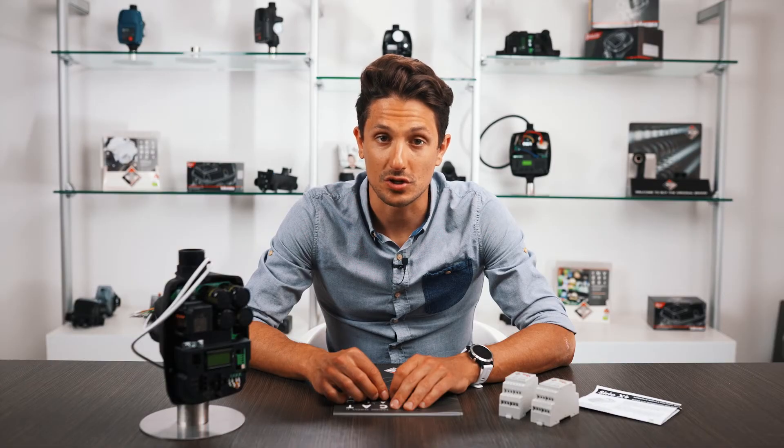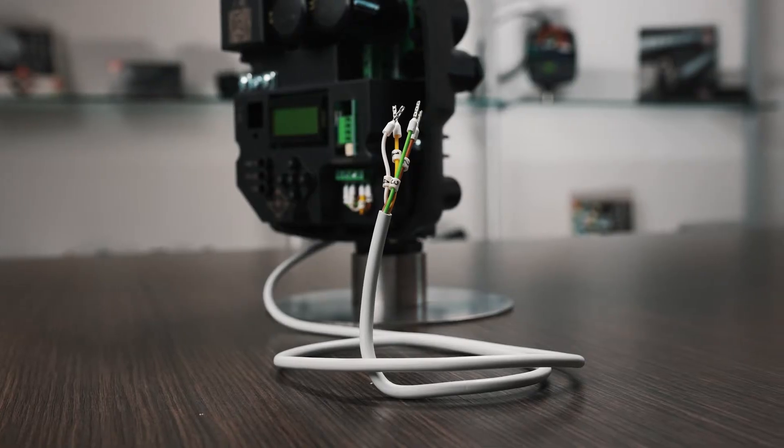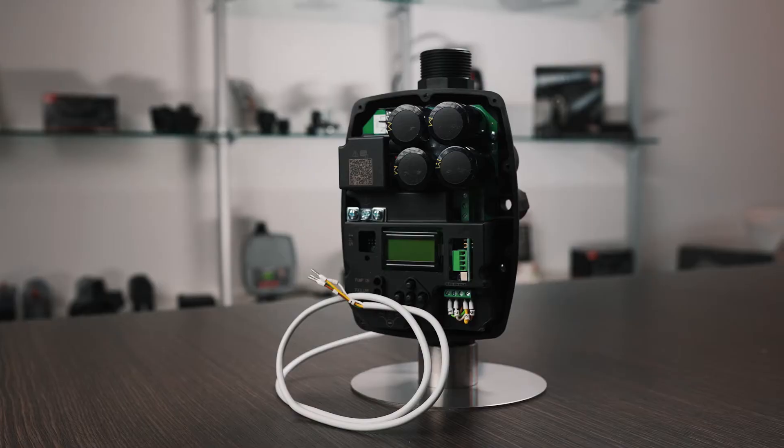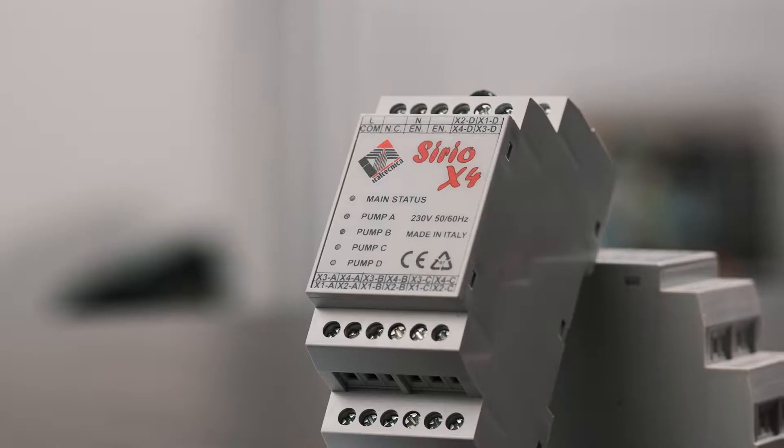If we have twin groups — meaning groups with two pumps — a device must be associated with each pump. A simple cable is enough to let the two Sirios communicate with each other, but if there are three or four pumps, the X4 module must be used, where the cable of each single Serio will be connected.